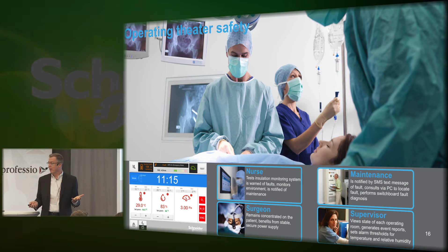So what we have here is a display, a simple display that goes into the operating theater that replaces about 5 different devices that are normally there. And to give that information to the nursing and clinical staff in a simple way that merely tells you what's going on with the electrical system. There's been a power failure in my operating theater. I'm on backup. How much time do I have left? In this case, it says 108 minutes before the lights are going out. Okay, so you don't have to worry about that.